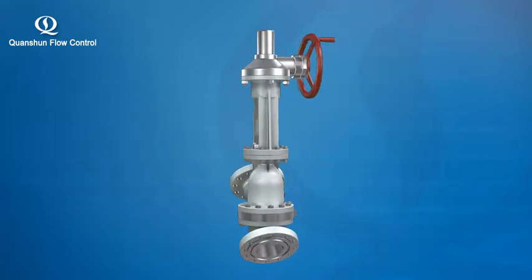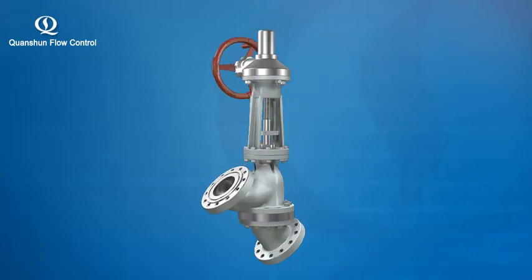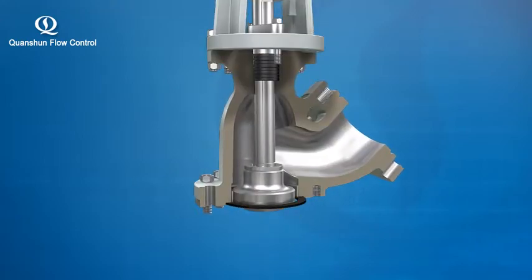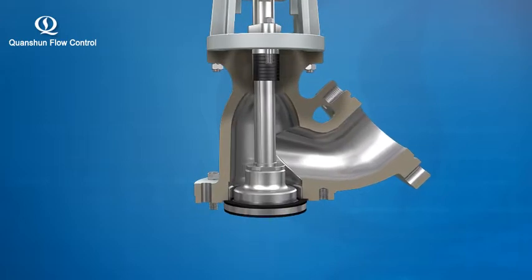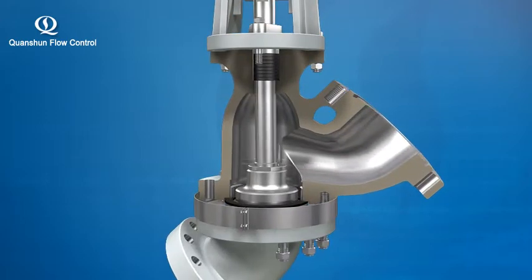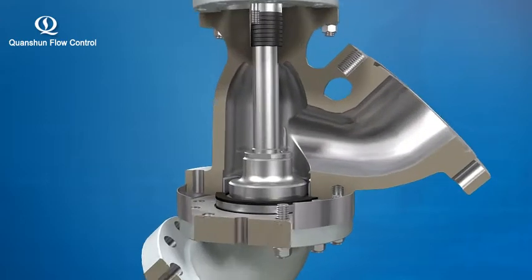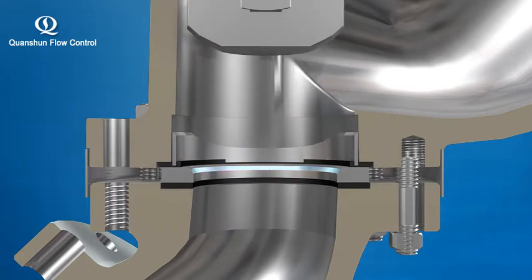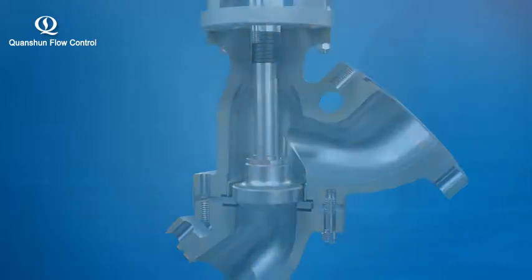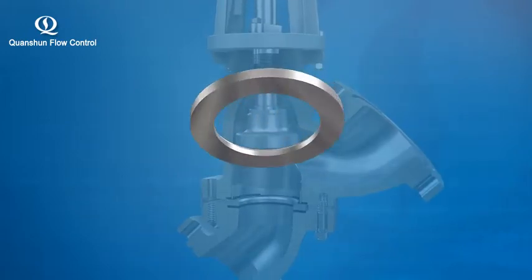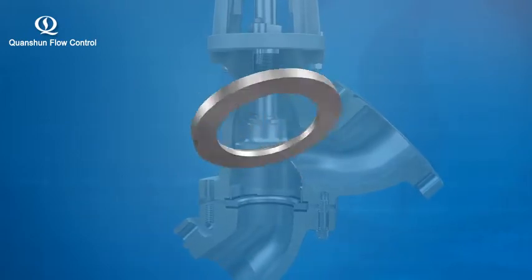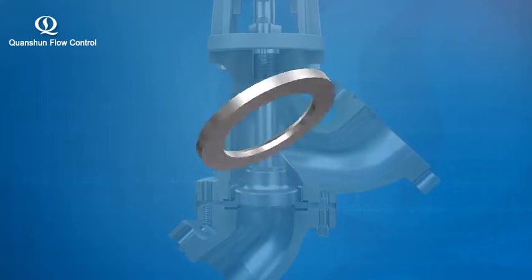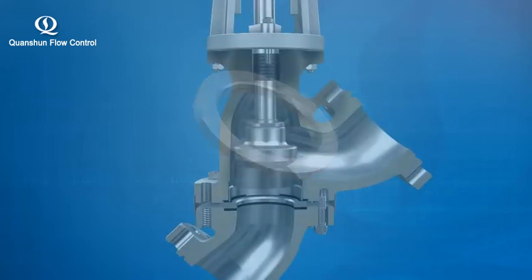3. The design of separated seat and body. The seat is kept centered relative to the stem and disc during assembly to achieve tight cutoff in the long run. The separated valve seat guarantees a uniform thickness of the weld deposit and the desired hardness after heat treatment in case of special alloy materials servicing, making it easy to conduct non-destructive tests on the seal face and allowing instant inspection and repair by removing the valve body connecting bolts.